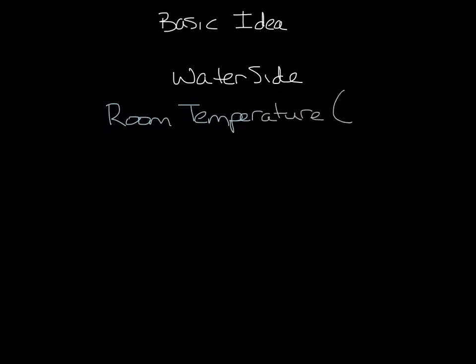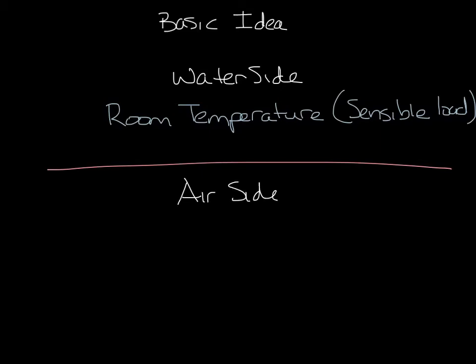The basic idea behind chilled beams is that the water side handles the room temperature, which is the sensible load, and the air side handles the humidity, which is the latent load, and the ventilation air.